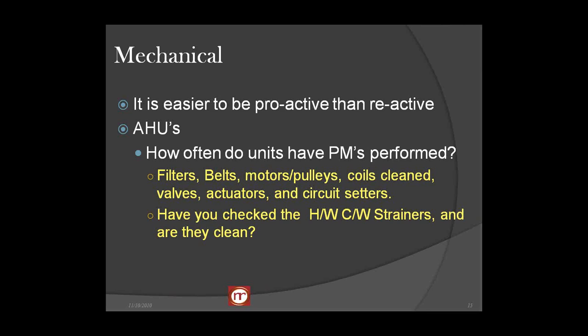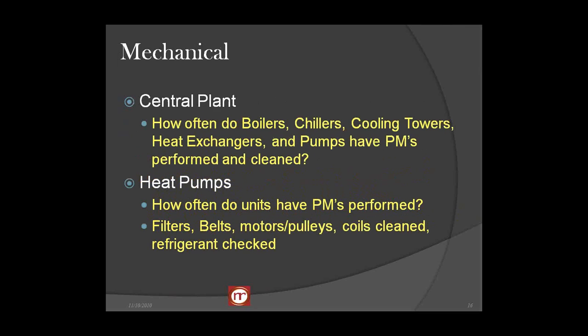A lot of times I talk to the guys and they tell me, well, we did all this stuff. Did anybody check the strainer? Most of the time they didn't. And about 90% of the time we can find a problem there. And the central plant, it's important for all your equipment to be cleaned, inspected, and running correctly. If you have a school that has water source heat pumps and you have a dirty heat exchanger, I can guarantee you're having a lot of problems and using a lot of excessive energy to maintain that building, if you can maintain it. Now with heat pumps, nothing different there.